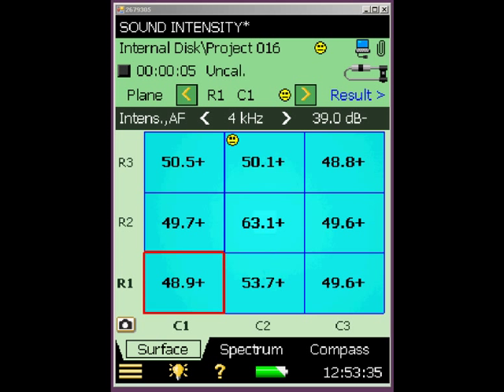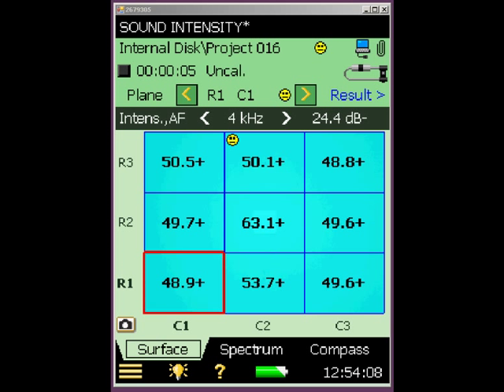Even if this measurement technique is new to you, it becomes immediately obvious where the acoustic problem lies on this panel. You can see that the center of the screen has the highest measurement value at 63 dB. So we have confirmed that the acoustic leak is in the center of the panel. It's important to have this numerical data, because if you modify this wall to improve the insulation, you'll want numbers to compare before and after to see how well you did the job. That concludes this part of the demonstration.